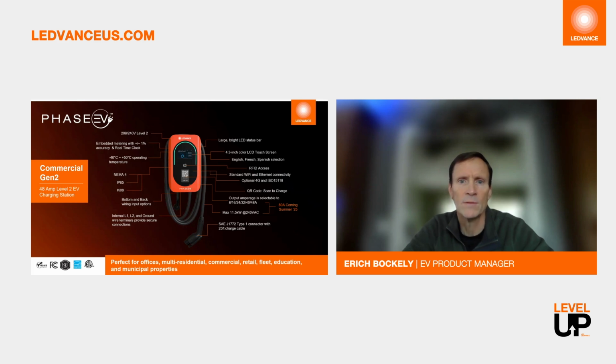These products today are 48 amps, but when they are being installed, there's a dial inside where they can be set from 8 all the way up to 48 amps in 8 amp increments. So that if you have an installation where you have less than a 60 amp circuit powering one of these, you can just choke back that amperage and use a smaller amount of current to feed the charger.